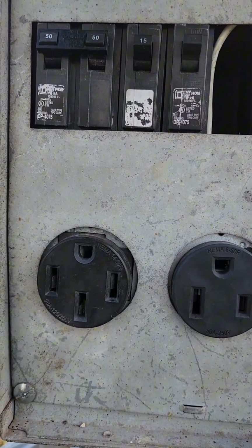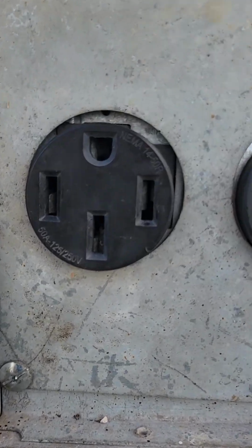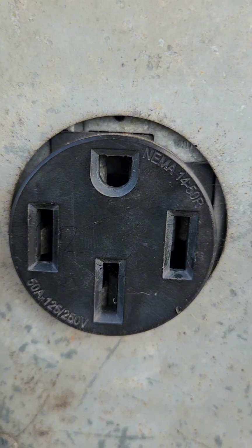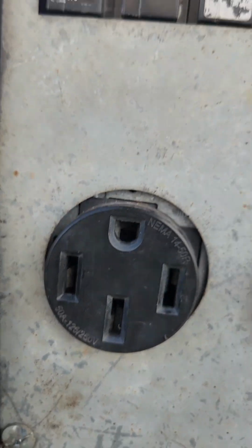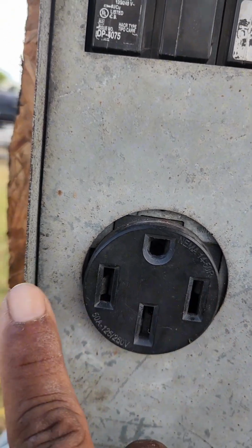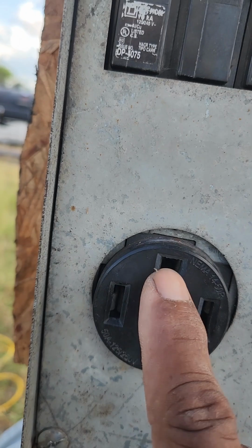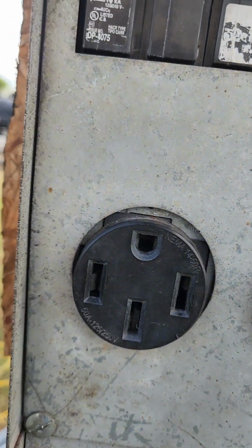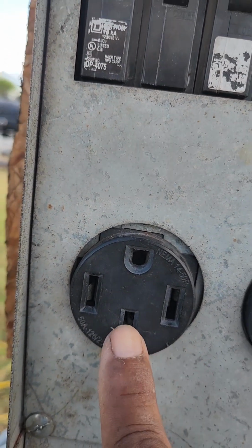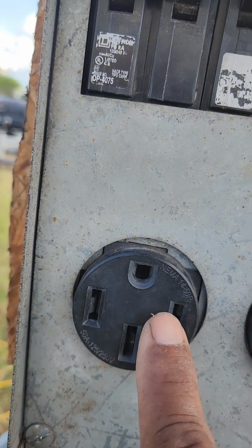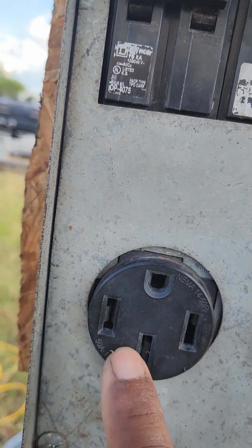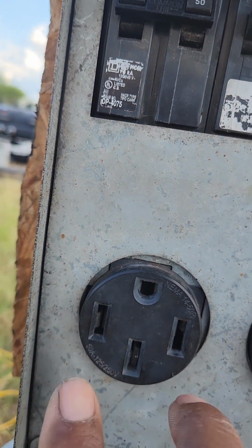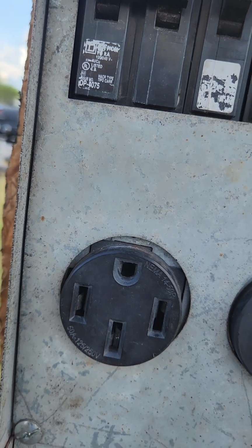Okay, we're going to go over our AC first. See this plug here? This is a 4-wire plug. So we have a hot, a neutral, and a ground. So 2 hots and a ground. This is a neutral. Neutral with that hot is 110. Neutral with that hot is 110. 2 hots together will give you 240.